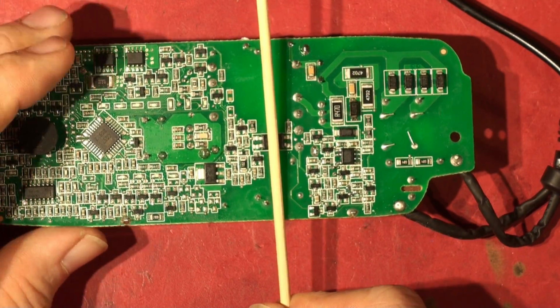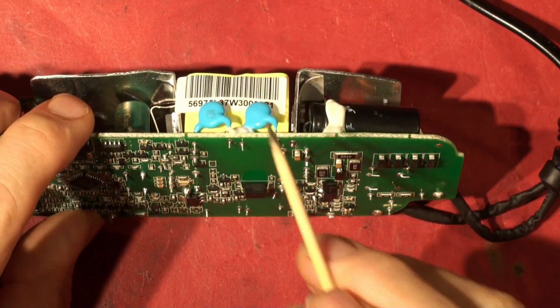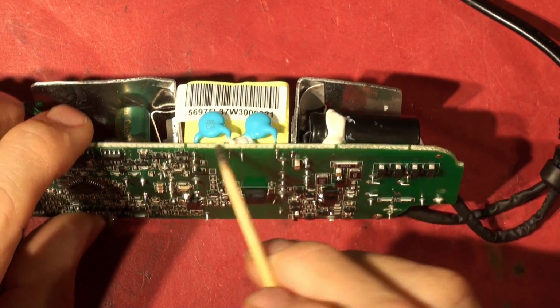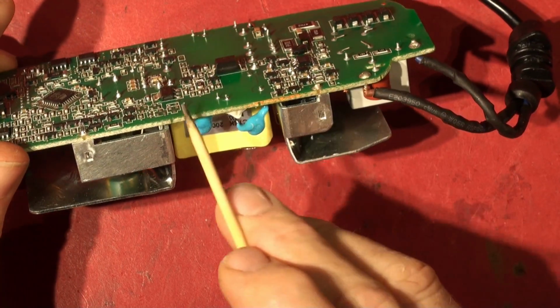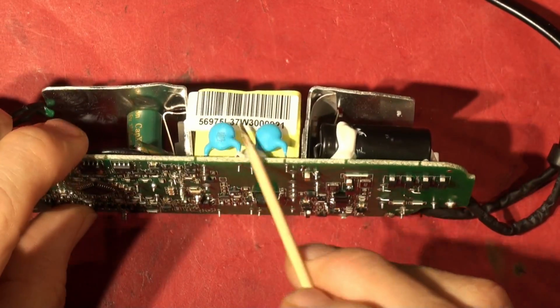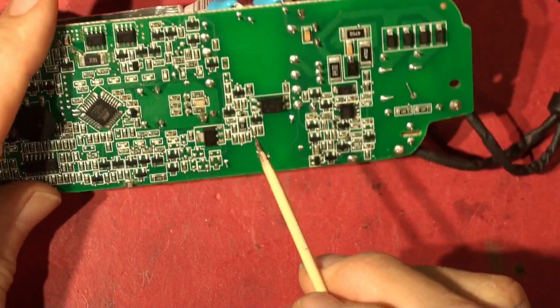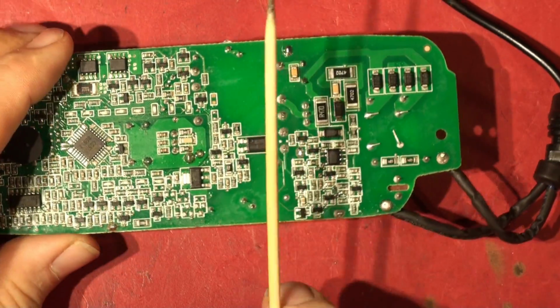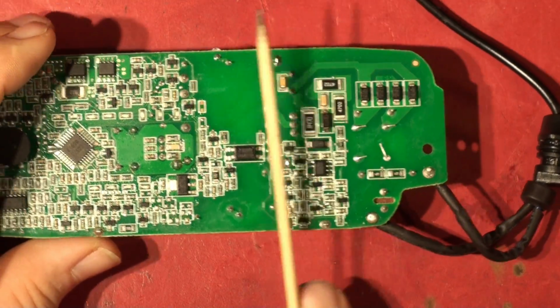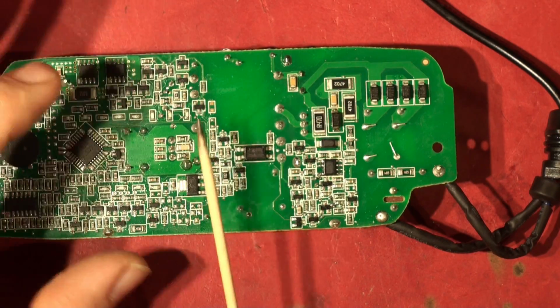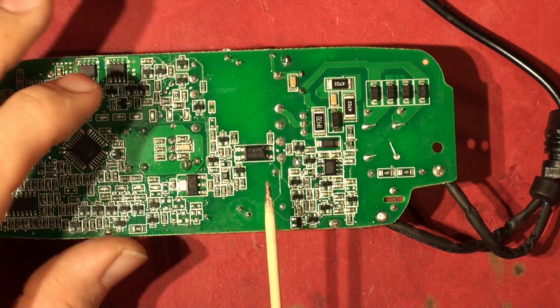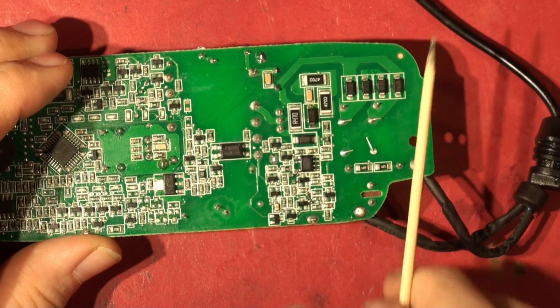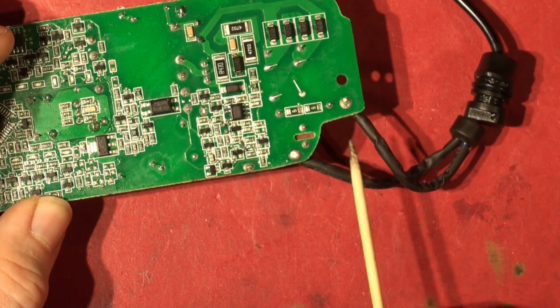There should be a 2kV isolation, except for these class Y capacitors, which are noise filtering capacitors. There's 2 on either side, and they're fail open, fail safe capacitors. Okay, so you should be able to put 2000 volts on this side and still touch this side with relatively small leakage, so it's a safety issue. But on this side, this is referenced to the mains, so there's your live and neutral coming in.